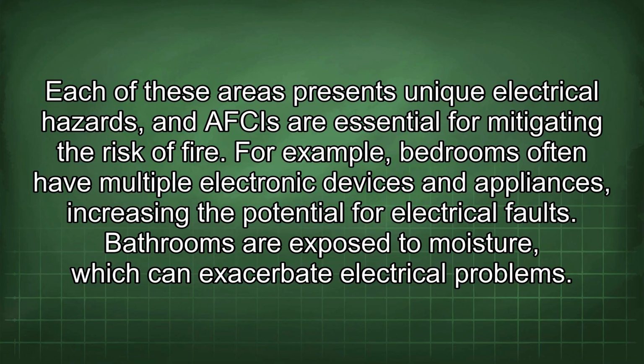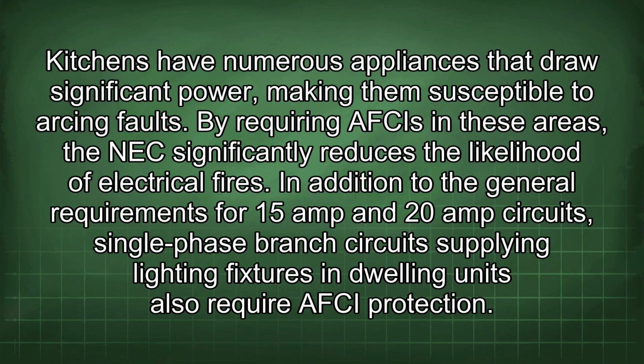For example, bedrooms often have multiple electronic devices and appliances, increasing the potential for electrical faults. Bathrooms are exposed to moisture, which can exacerbate electrical problems. Kitchens have numerous appliances that draw significant power, making them susceptible to arcing faults. By requiring AFCIs in these areas, the NEC significantly reduces the likelihood of electrical fires.